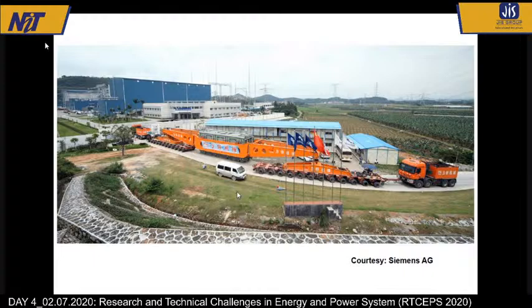Now if you consider a 400 kV, 200 MVA transformer, that will go up to 15 to 20 crores at least, or more. Does anybody keep such a transformer in a godown? No, no power company has that much fund reserve to keep it in storage. Second point: if the transformer goes faulty, can you go to the market and buy another one? No, it's not a laptop that you just go and buy. You have to place an order and it will be manufactured, taking 5 to 6 months before you get it. So it is almost imperative that we protect this transformer against faults.